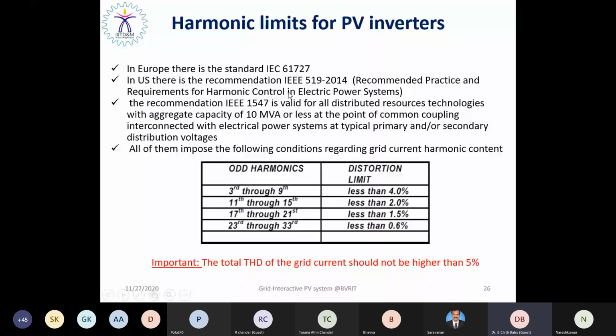So all of them impose the following conditions regarding grid current harmonic components. You can see the level of the harmonics. In the lower order harmonics, you see the level of the limit. The total THD of the grid current should be less than 5%, as per the IEEE 519-2014 standard. Please keep in mind that any control algorithm can be developed for a grid interactive power converter, but care should be taken that while injecting AC power into the utility grid, the injected grid current should have a THD of less than 5%.